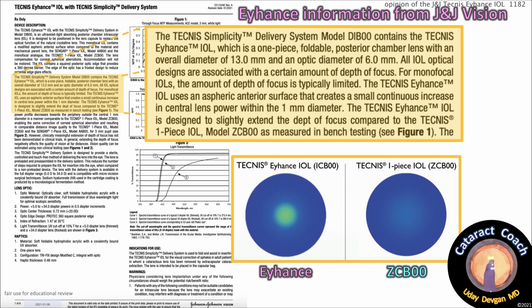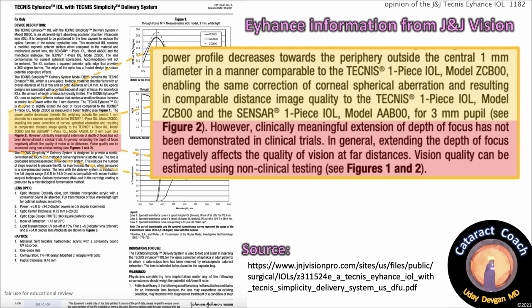Here are the pictures from Johnson & Johnson. You can see the Eyehance in the center — that green zone is a 1mm zone where there's an increase in curvature or power, and that anterior surface is altered. 85% of the optic is the same. The power profile decreases towards the periphery outside the central 1mm diameter in a manner comparable to the TECNIS one-piece IOL ZCB00, enabling the same correction of corneal spherical aberration.